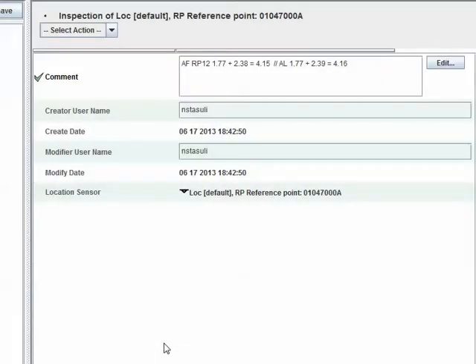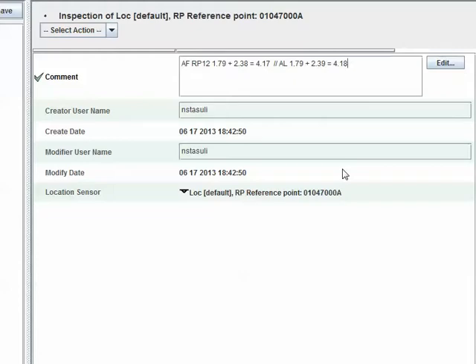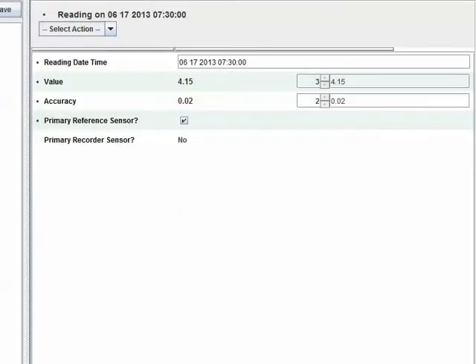Here we are at the sensor inspection for that reference point. We will update the reference elevations and correct the math for the as-found and as-left readings. Then we need to go update the sensor readings themselves. The as-found reading is now 4.17 and the as-left reading is now 4.18.